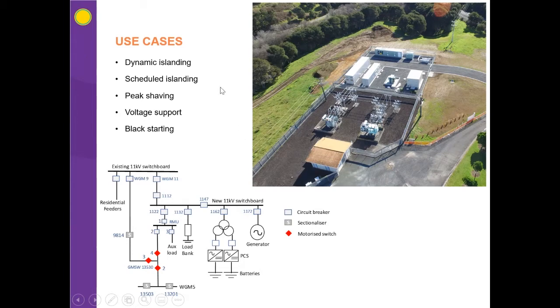It was intended to be used for dynamic islanding. The battery is connected to the network, which is fed from the 33 kV system through a couple of transformers and feeds the CBD through this Hetherington Road feeder. If the storage management system detects a loss of voltage on the 33 or the 11, it opens the circuit breaker and the battery continues to feed the CBD of Whangamata. It wasn't intended to feed the whole town, only rated for 2 megawatts, enough to feed the CBD for about 2 hours. If the line hasn't been brought back by then, our operators have the option of starting the diesel generator.